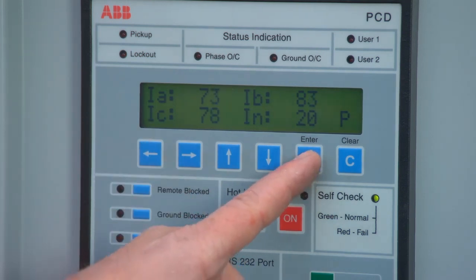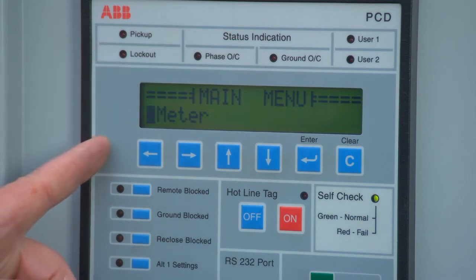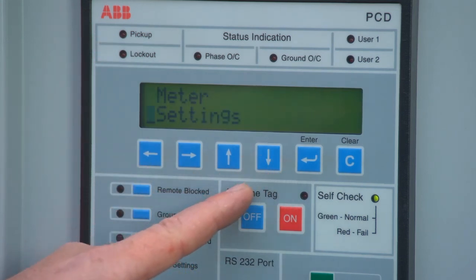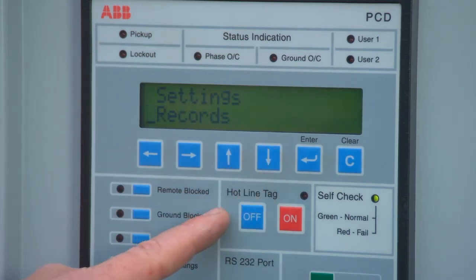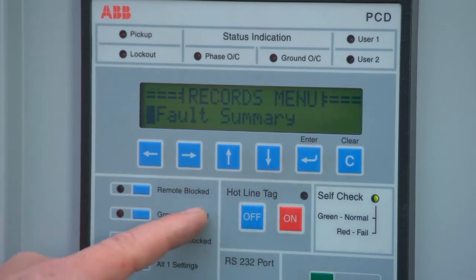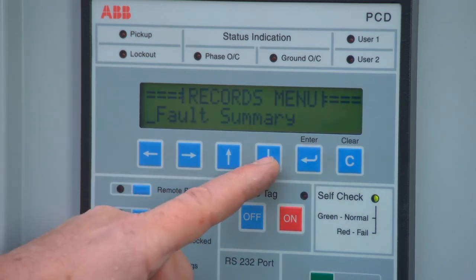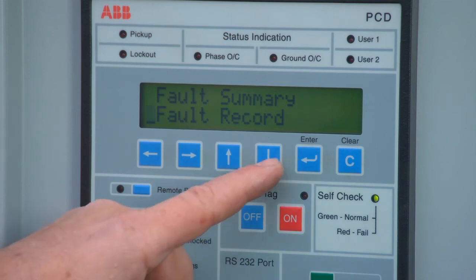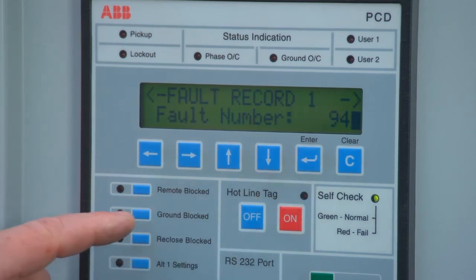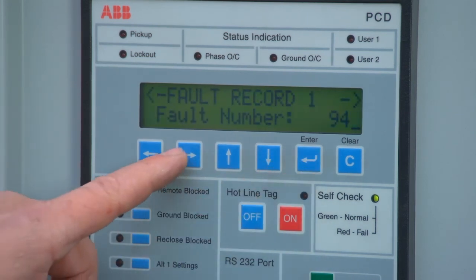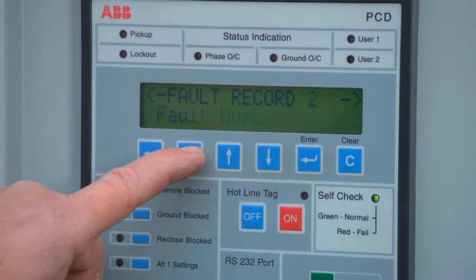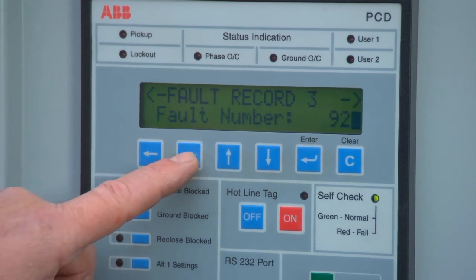Pressing the Enter button once will display meter. Now, scrolling the down arrow, we can scroll to Meter, Settings, and Records. Now, pressing Enter will display the fault summary. Pressing down from here will display Fault Record. Now press Enter to display the number of faults recorded. The left and right arrows will now scroll through the desired fault record.